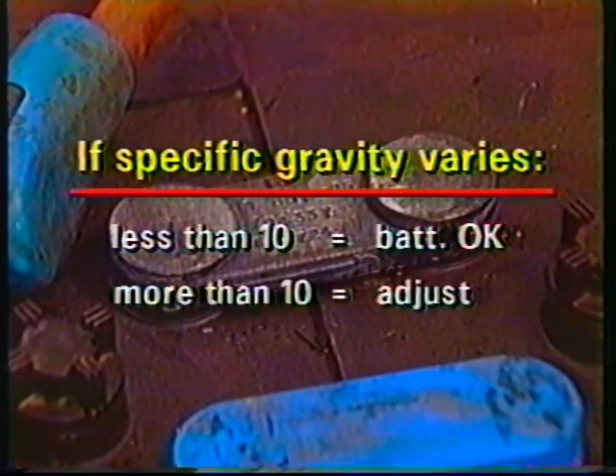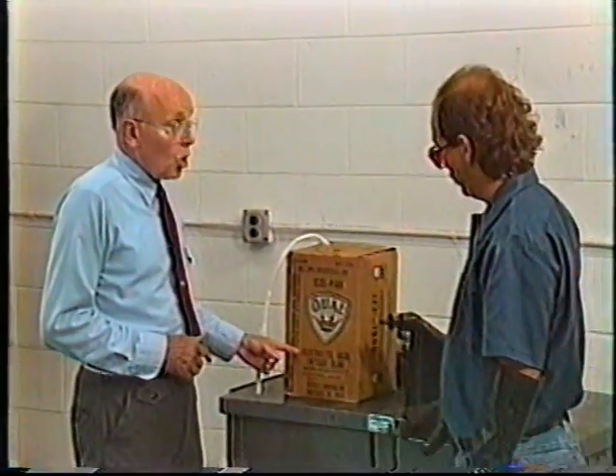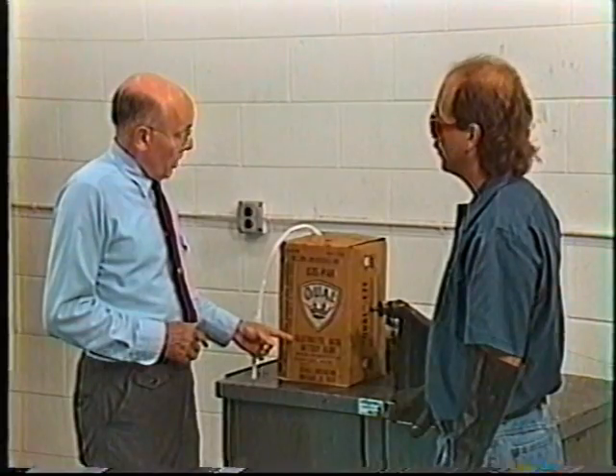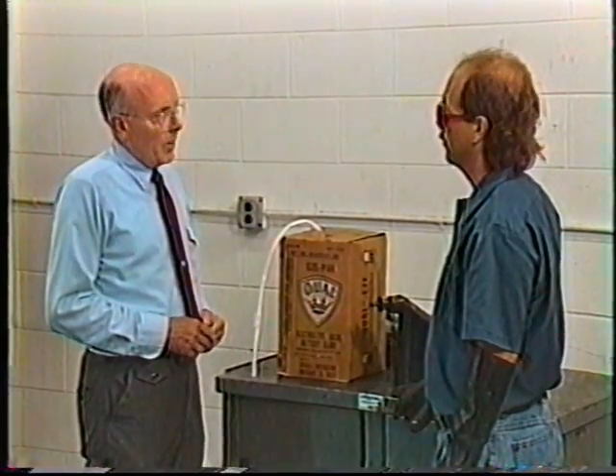If there is a difference of 10 points or more, you have to adjust the cell's specific gravity by either raising or lowering its value to meet the listed number. For example, if a cell's specific gravity is too low, we need to raise it by adding 1.400 electrolyte, which is the recommended electrolyte number for lift truck batteries.